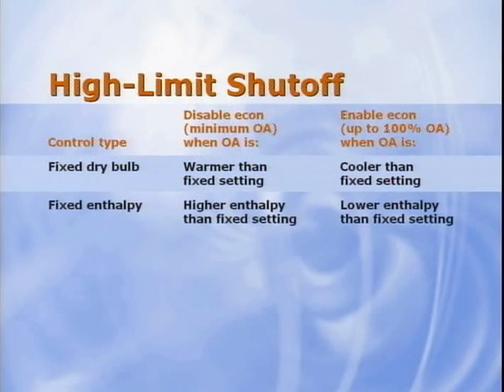Fixed enthalpy control uses sensors to measure both the dry bulb temperature and humidity of the outdoor air. The controller then calculates the enthalpy and compares it to a predetermined high limit shutoff setting. The economizer is disabled whenever the outdoor air enthalpy is above this limit. This method requires an added humidity sensor, but for a VAV system, in most climates, fixed enthalpy control saves more cooling energy, so it might be worth the added first cost.